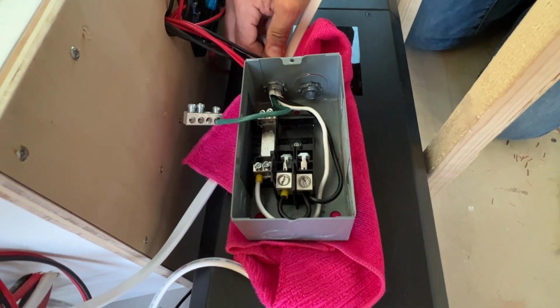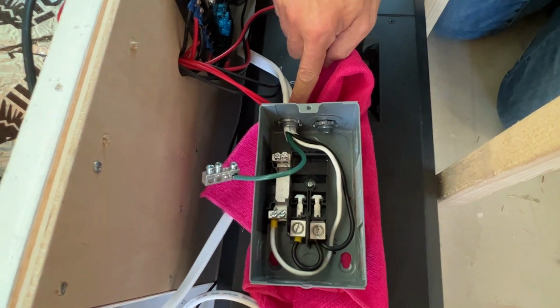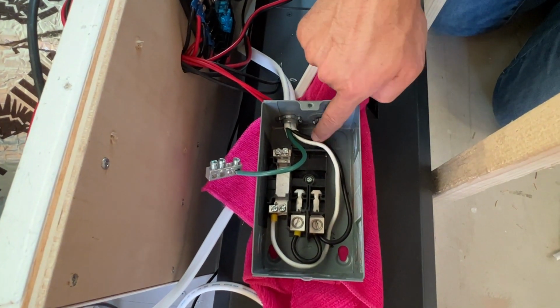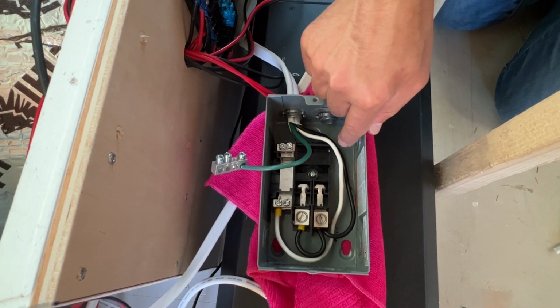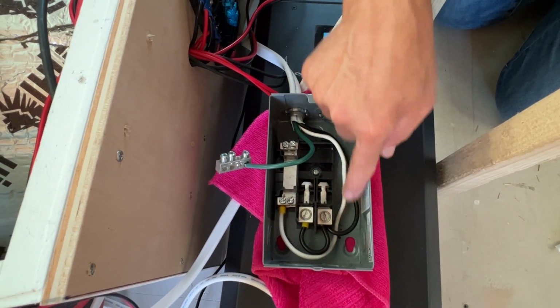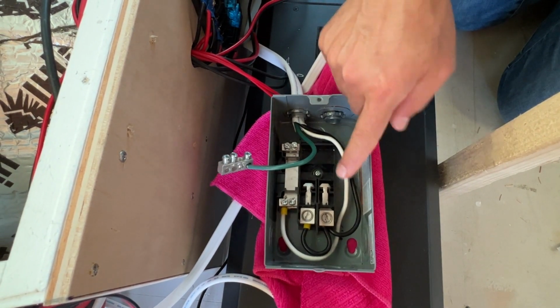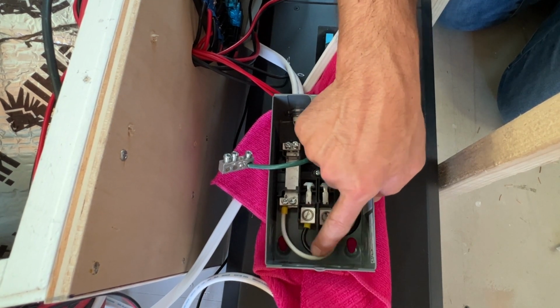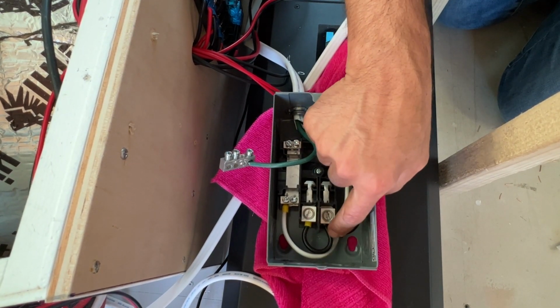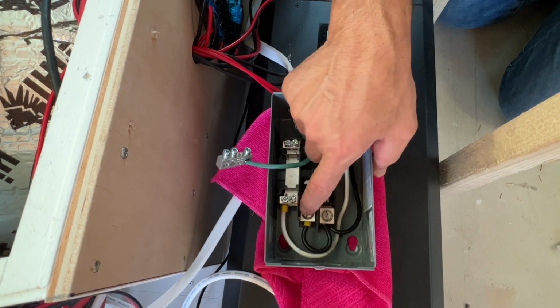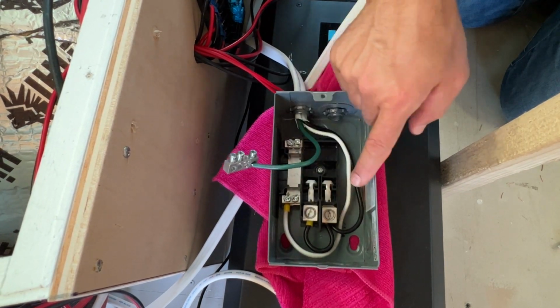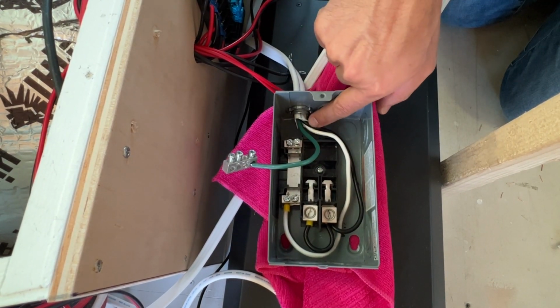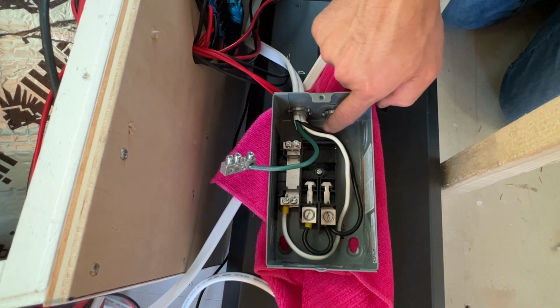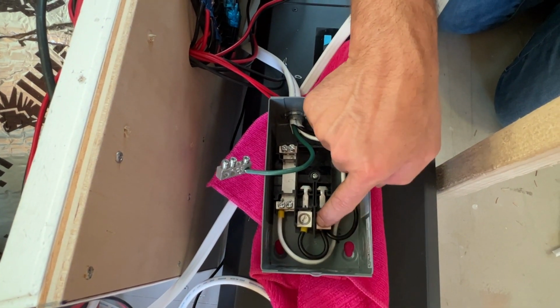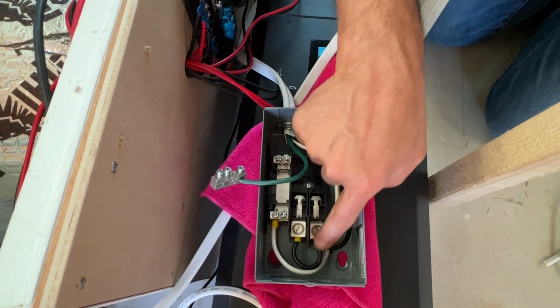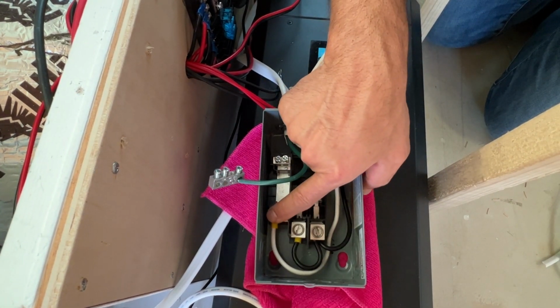And I fed in that 10 gauge wire. Here's the wires that come out of it. So I realized pretty quickly that those two pigtails were going to take up way too much space in this box. So I went ahead and just ran a jumper cable between these two. This is also 10 gauge wire between these two positive terminals. And then the main wire comes back to here. So we've got the positive, we've got the hot wire that feeds these two terminals. We've got the neutral wire that runs to the neutral bus bar, which is here.